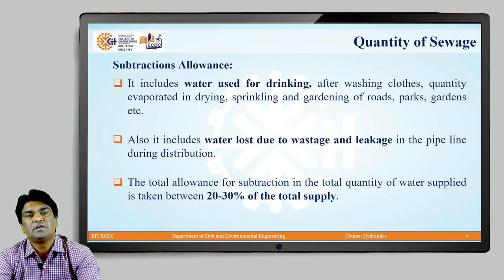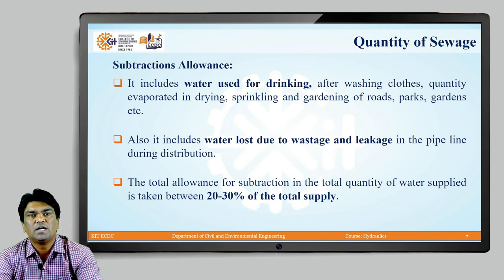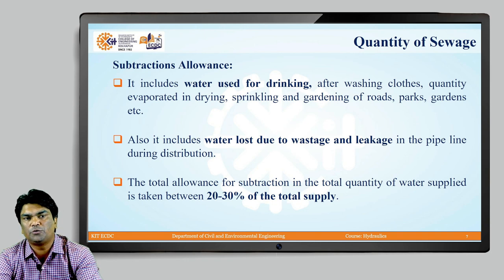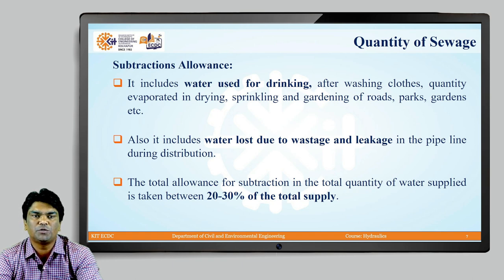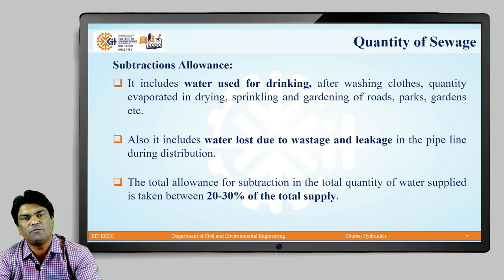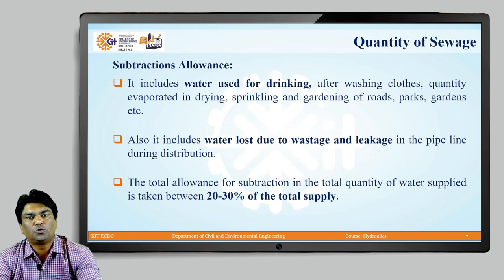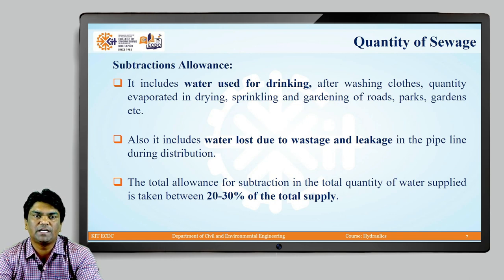The next consideration is subtraction allowance. It includes water used for drinking, water used for washing clothes, quantities evaporated in drying, sprinkling and gardening of roads, parks, and gardens. Around 70 to 80 percent of water is converted into sewage, and the rest is utilized for other purposes — these are considered subtraction losses. It also includes water lost due to wastage and leakages in the distribution pipeline. The total allowance for subtraction is taken as 20 to 30 percent of total supply.